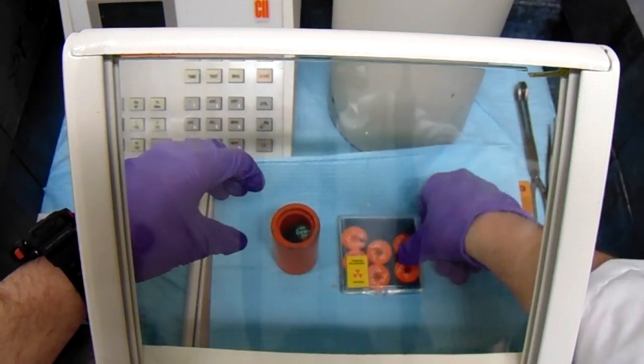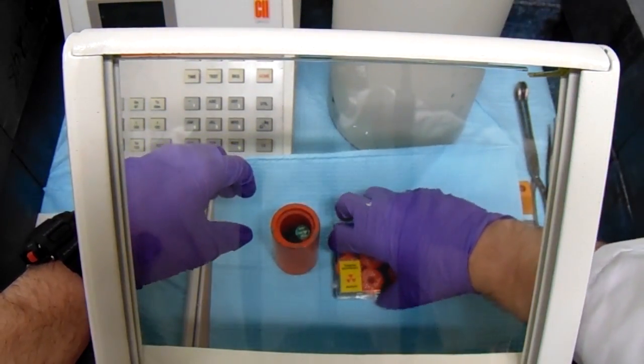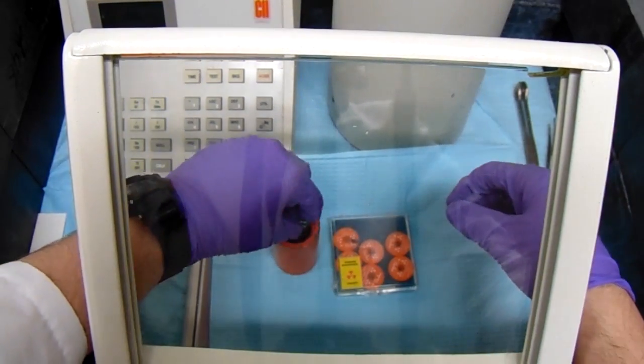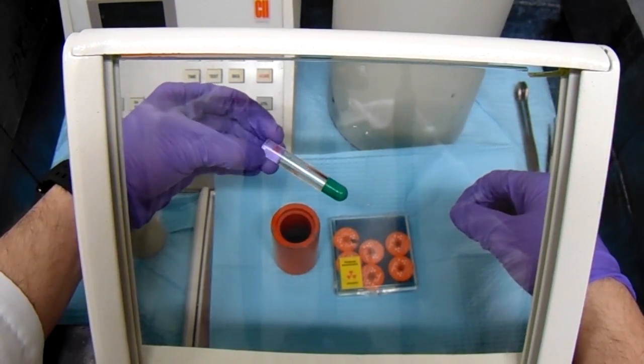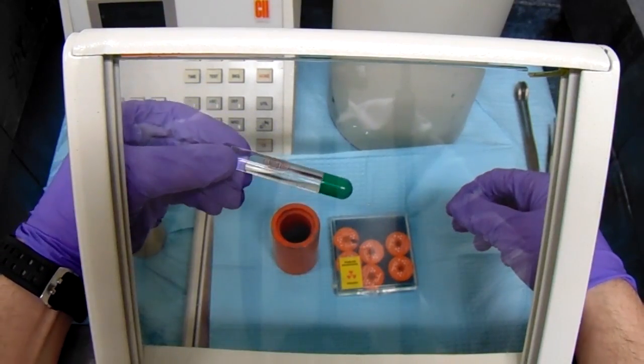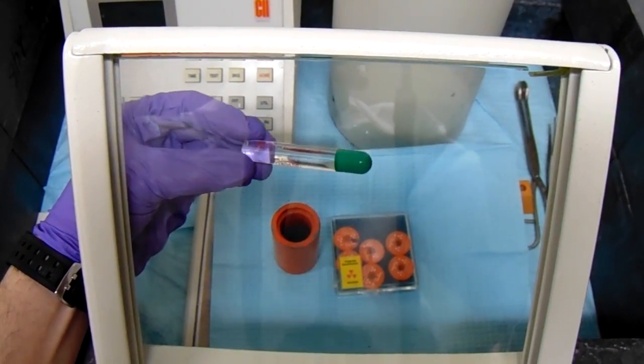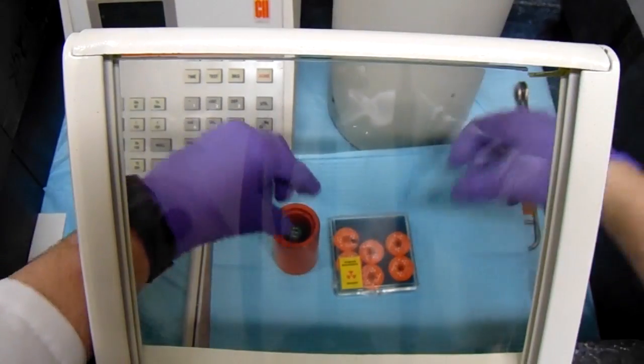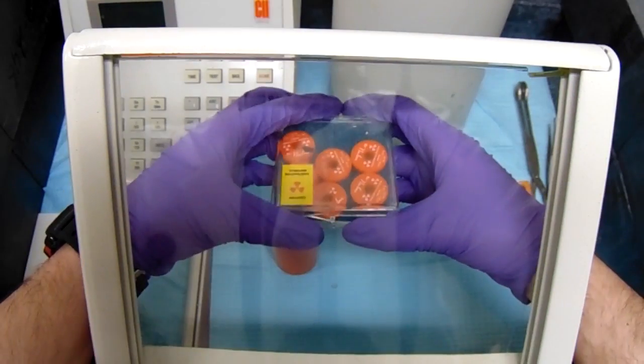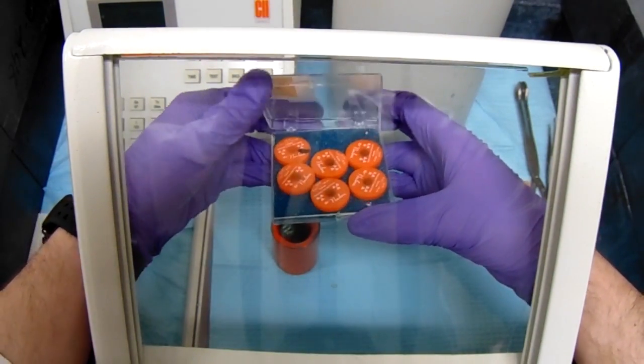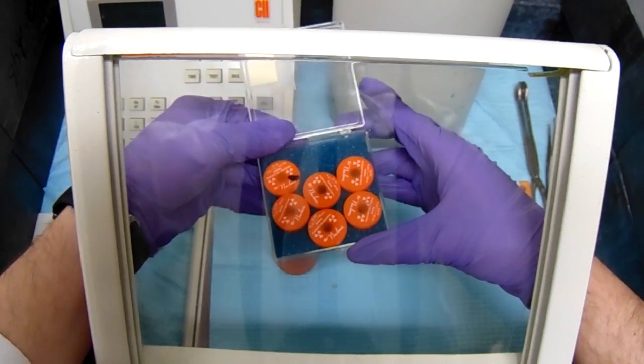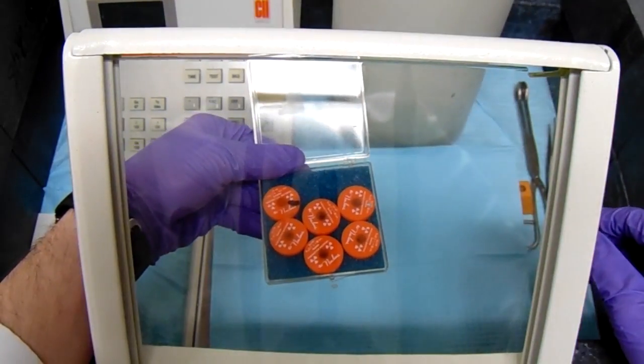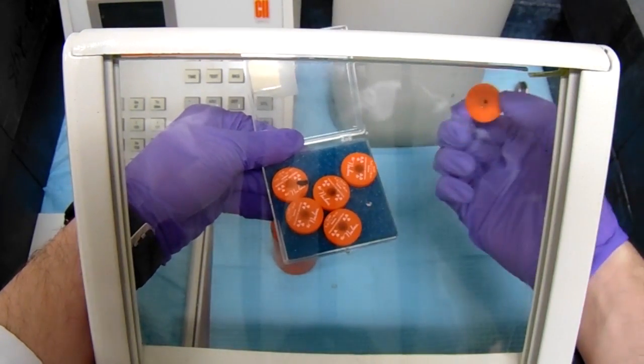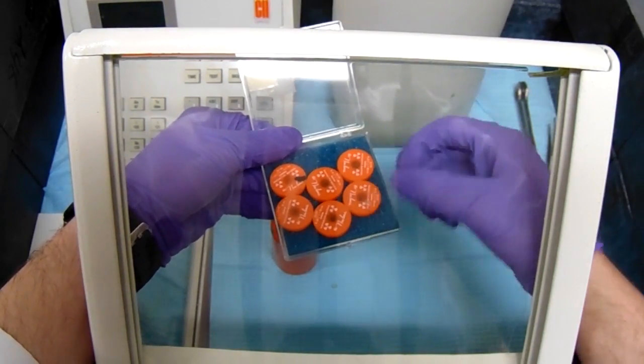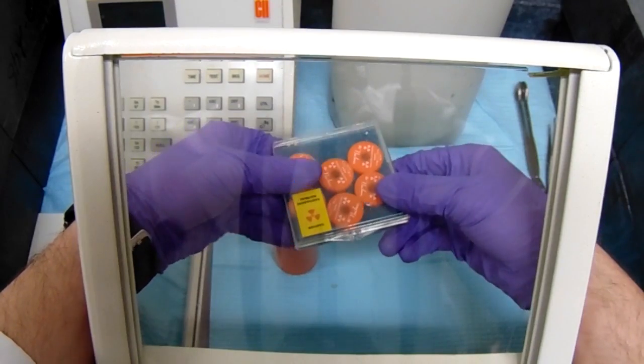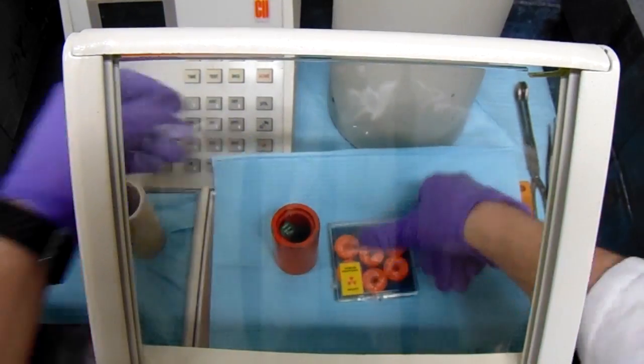Now, to do well counter constancy, we use our bar cesium source and our 5-disc cesium sources. The bar source is just a plastic bar with a cesium isotope in the bottom. At any point now you can talk about the half-life and energies of cesium, talk about why we use it. These are the 5-disc sources and one cobalt source, but the cobalt source has a black mark on it, so you don't get it confused and use that to do your constancy on the well or probe.